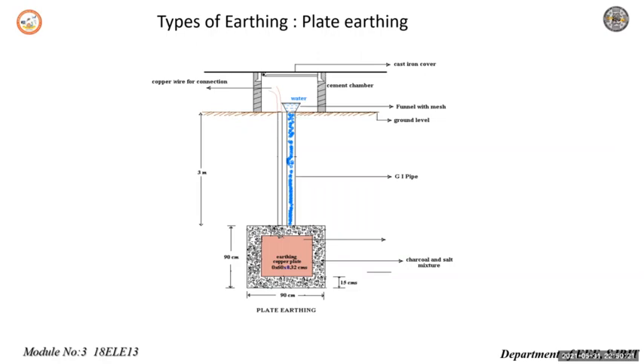The connection of electrical machinery to the general mass of earth with a conducting material of very low resistance is called earthing or grounding. The earthing of electrical equipment brings the equipment to zero potential and avoids shock to the operator under any fault conditions. Then what is the necessity of earthing?